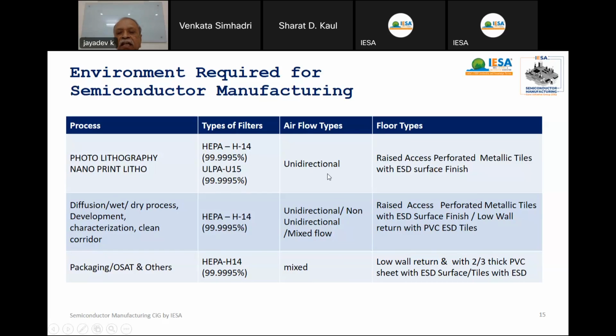And unidirectional. Normally people mistake what unidirectional is. The flow of the air is in one direction, either top to bottom or from one end to another end horizontally. So unidirectional flow is when the air flows from the ceiling to the ground, with lines perpendicular, the laminar flow. Normally we achieve this by maintaining 90 plus or minus 20 feet per minute. So the full roof will be covered with HEPA filters. Air flows down to the perforated raised access flooring and goes back to recirculation. And we have to properly adjust the airflow pattern such that vertical laminar flow is achieved.